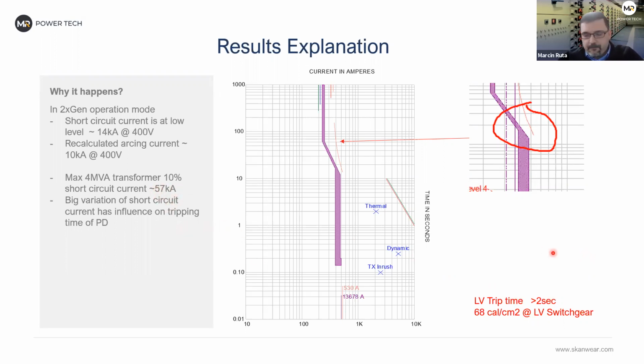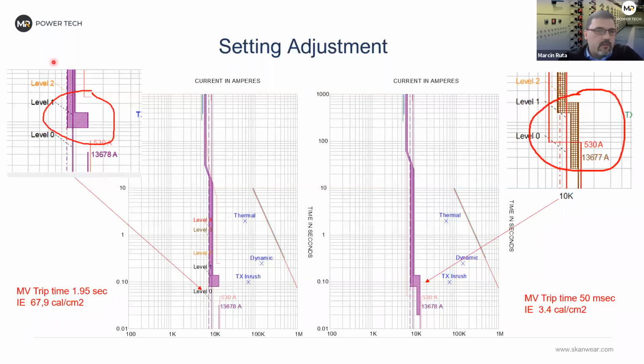So just to fix it, the first idea was to modify the low voltage breaker settings, but we found that there is some limitation because it was a very low arc current, so we barely see any difference. We still are somewhere in this 2 second area as a fix. Normally it would be around 20. So it didn't really help very well. The same situation applies if we use zone selective interlock for these 2 scenarios. For all the other scenarios this will work very well, but not for the 2 generator operation mode.